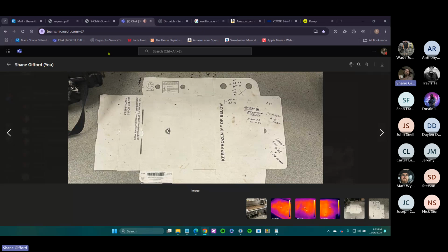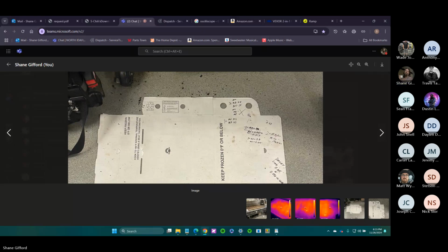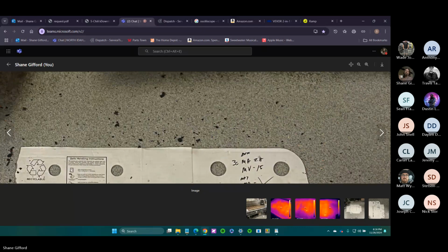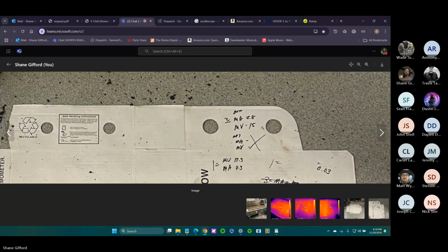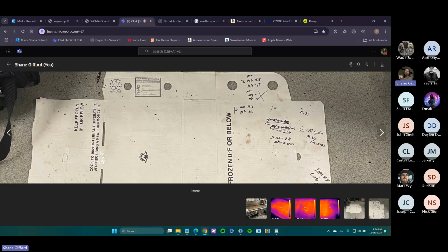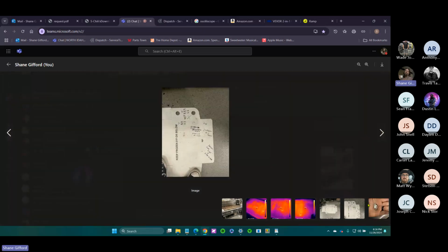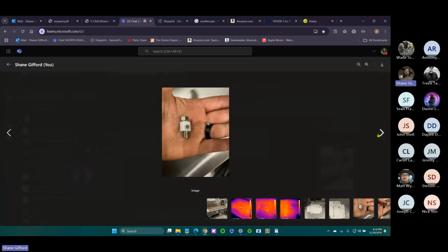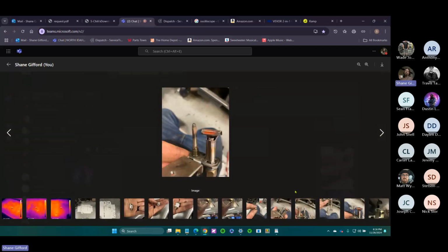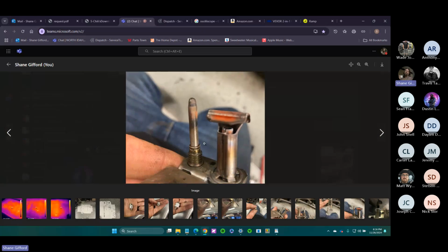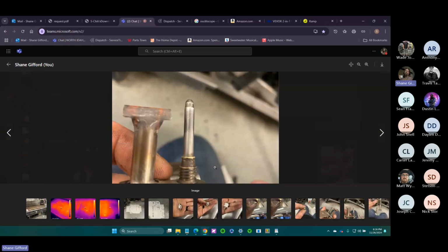So in this case, I pulled and cleaned every single thermocouple on this griddle. There were 4 of them, no, 5 of them, yeah, plus pilots. So pilot assemblies, we got milliamps, millivolts, and I like to do before and after. So when you're looking at your pilot assembly and you pull it out and it looks freaking nasty, like this guy. I mean, look at that, dude. That thing doesn't look like it's going to be producing much. What it should look like is that nice and shiny.